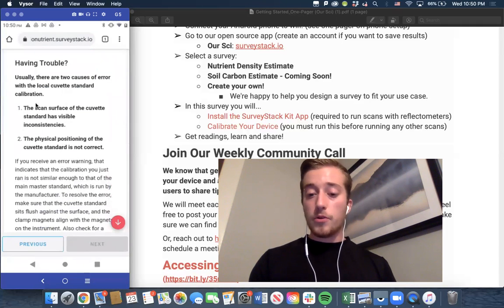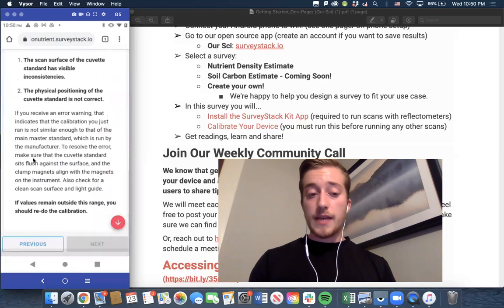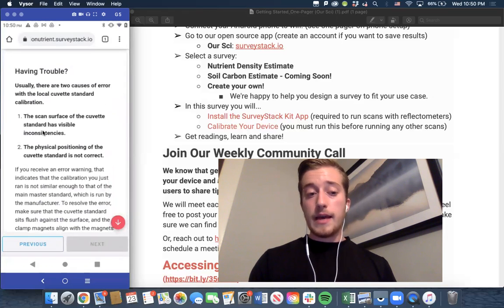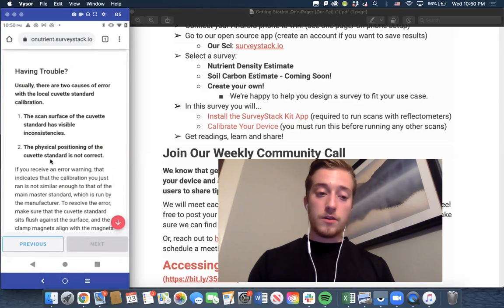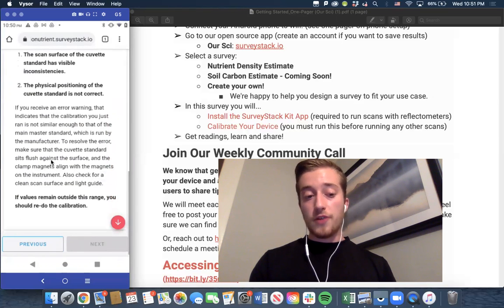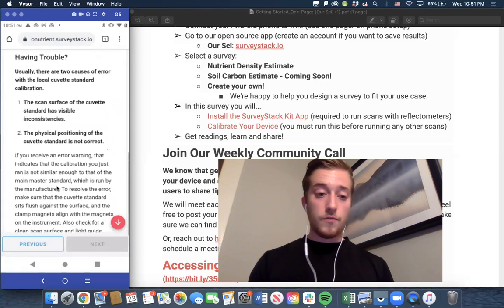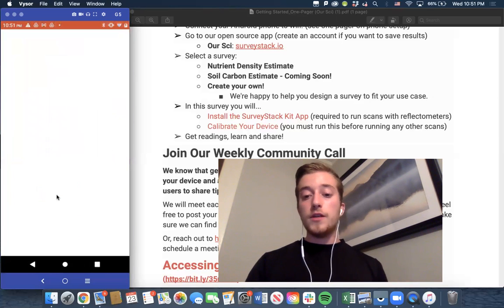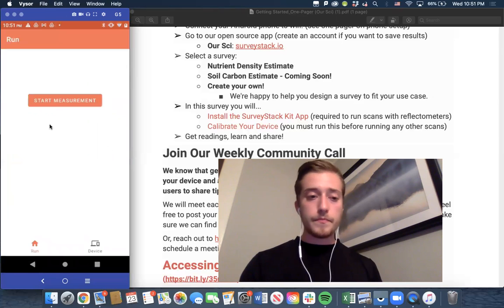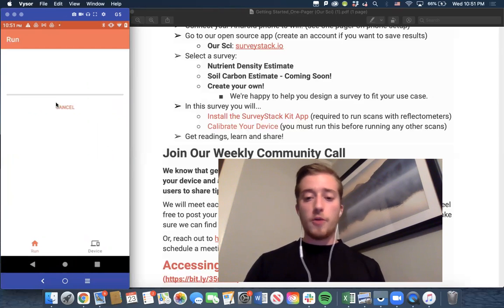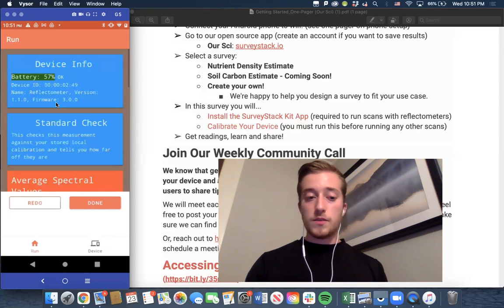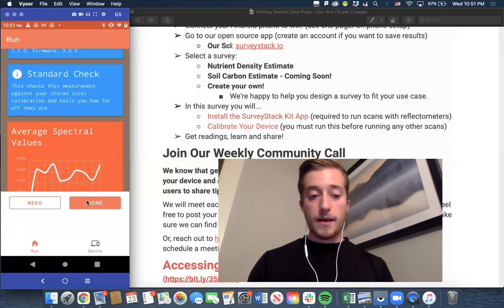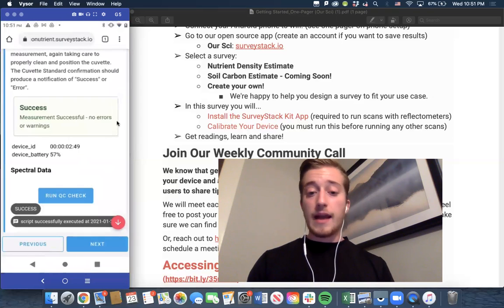If you end up having trouble or getting errors, there's some text below that has to do with, again, making sure that the cuvette standard is clean, positioning correctly. And then if you continue to get errors and you really can't get it, you might need to redo that initial cuvette standard scan. Just go back, redo that, resave it, and do a new quality check. So fingers crossed this works, but if not, I can always go back. So I'm going to click done, and I have a success.